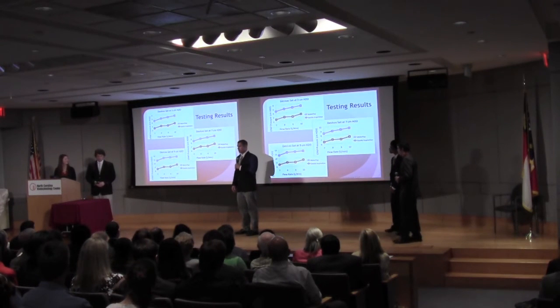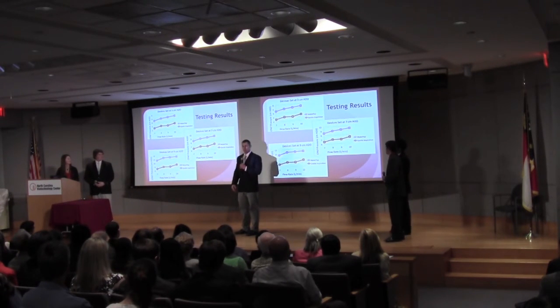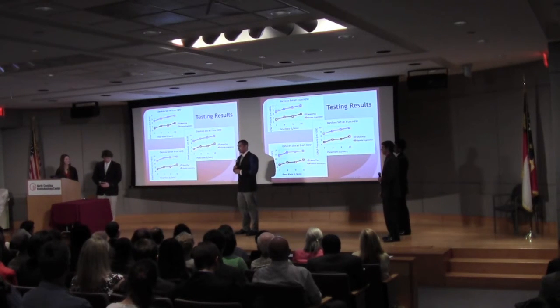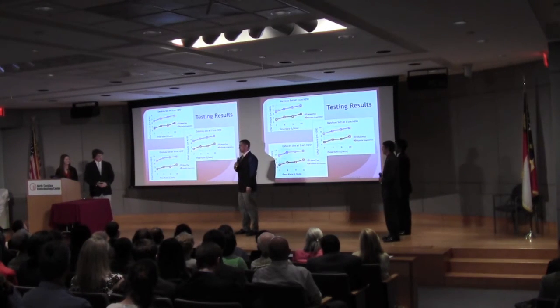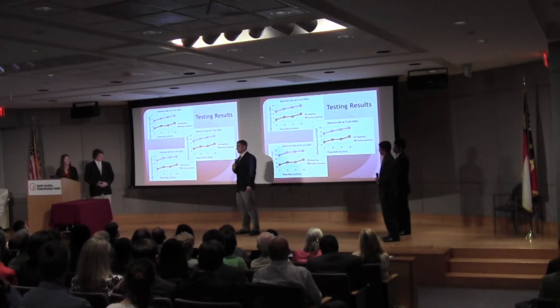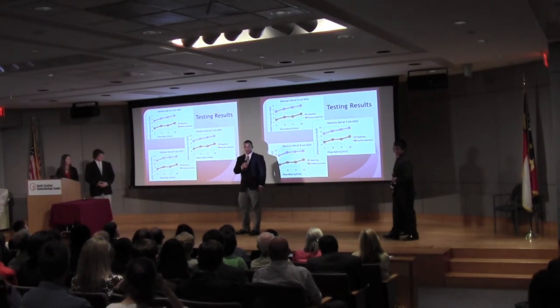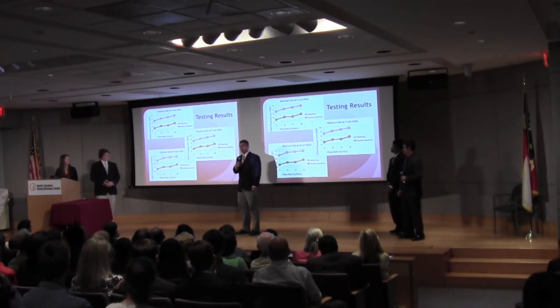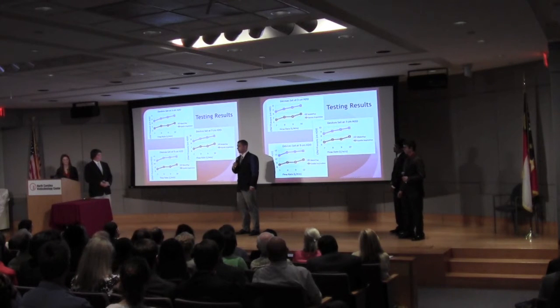So these three graphs show the actual CPAP pressure that is being delivered over a range of flow rates. In the NICU at WakeMed Hospital, the nurses typically use a flow rate of 8 to 9 liters per minute. In these graphs, the red lines indicate our device, Gentle Inspiration, whereas the blue lines represent the WaterPAP system, which is the current device used at WakeMed.